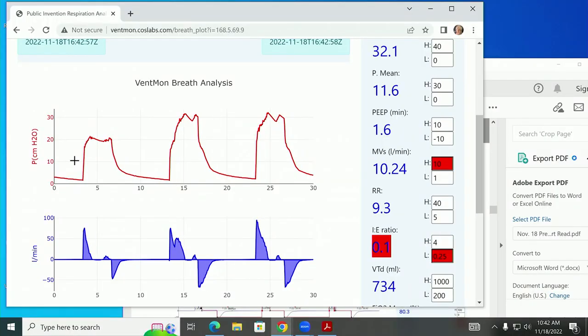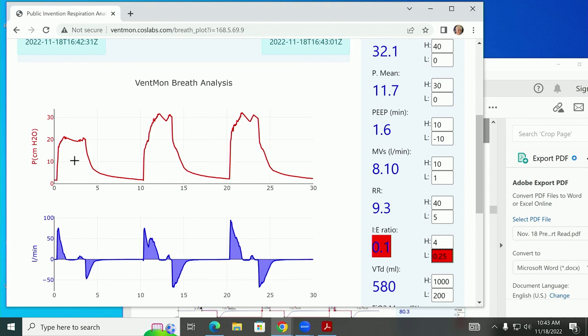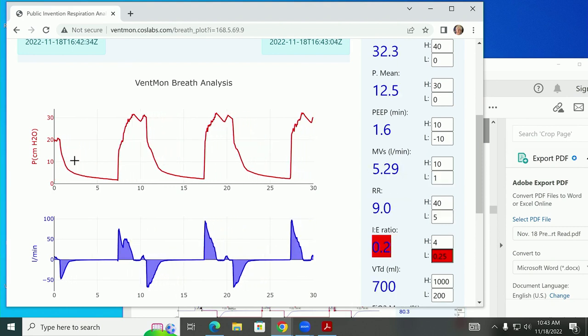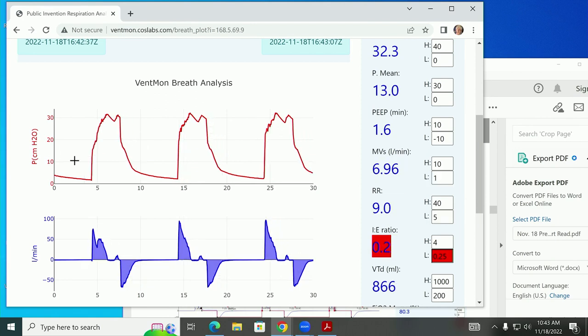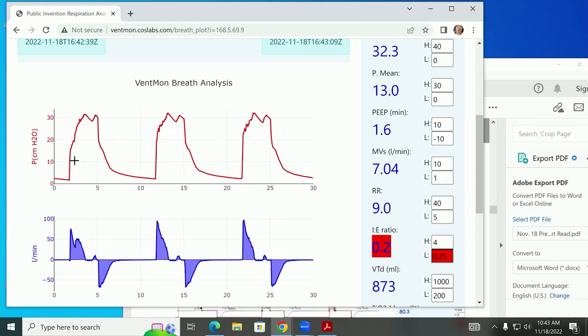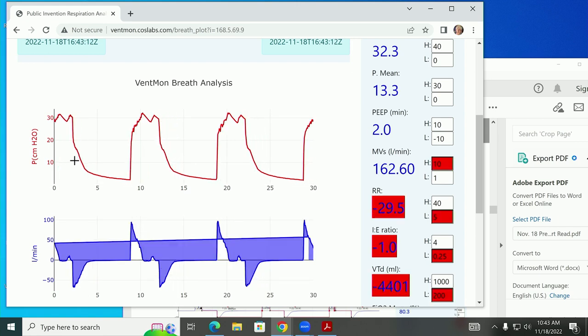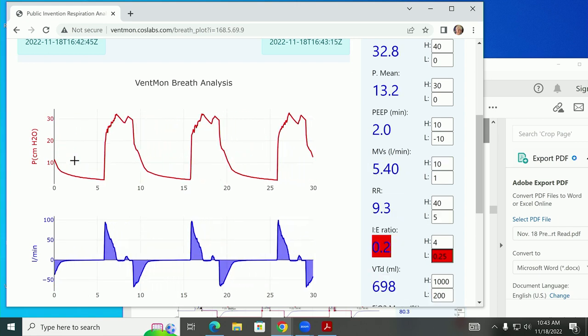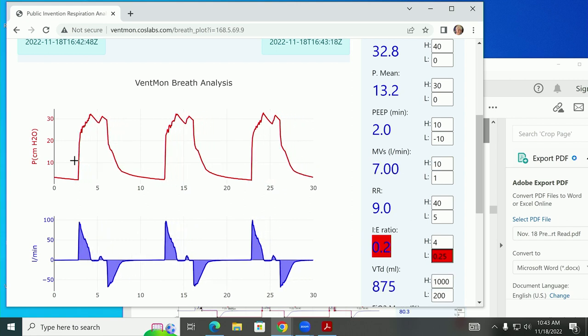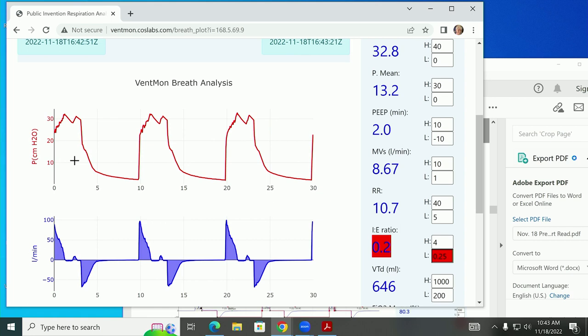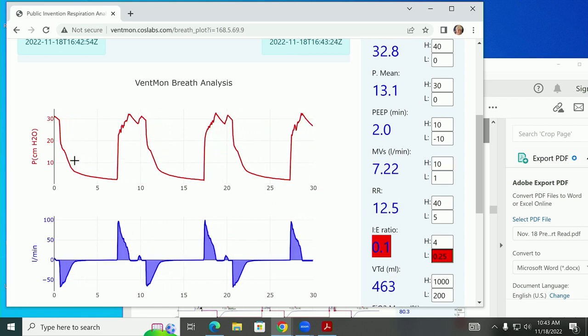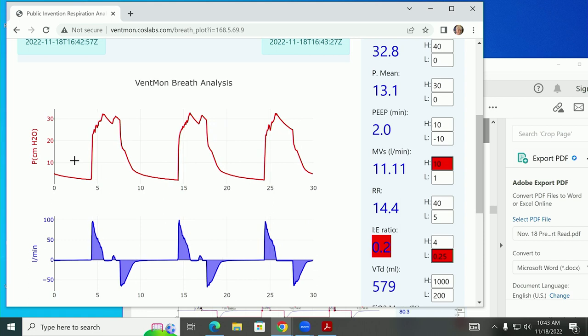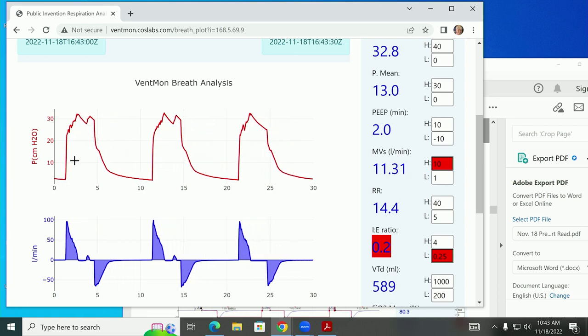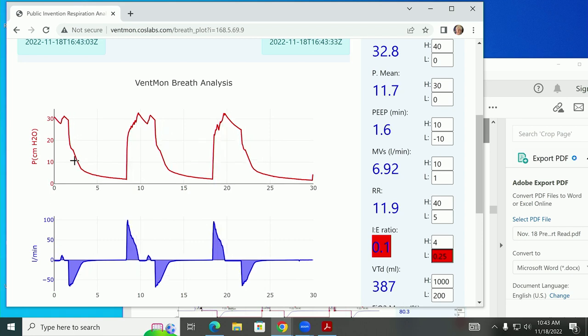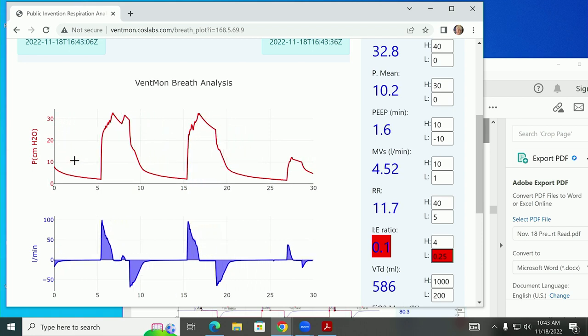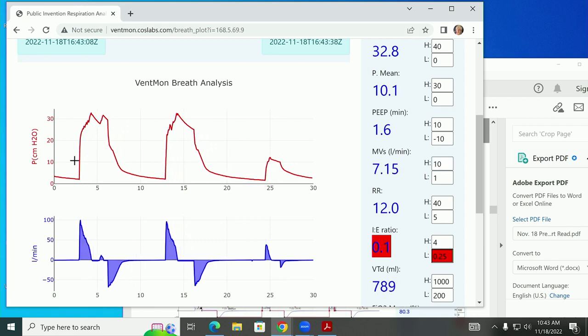This tank is currently at a pressure of probably around 30 psi, where the air-oxygen mixture all mixes together very well on its own. That mixture comes out through this tube, goes through, and goes to our proportional valve. This is really the core of the ventilator, this metal-colored valve right here. It's controlled through a PID loop to make sure it keeps the pressure as flat as possible. This is a pretty big programming challenge, but it's one of the big things that VentOS does.